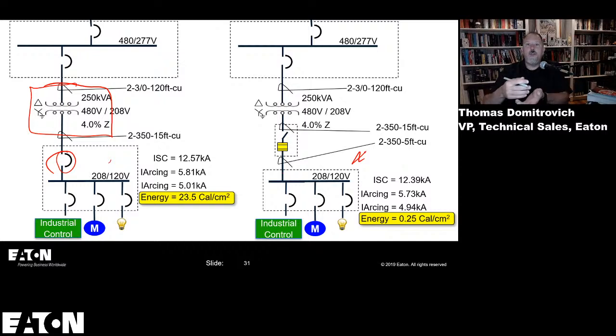I mean, even if you established an electrically safe work condition, you still have to dress and get in there and put your test probes on to make sure you turned the right breakers off, you locked and tagged the right breakers off, and all that great stuff as per NFPA 70E. By pulling this out, you have a local disconnect right next to that panel board. And it could be a panel board, it could be anything. It could be a piece of equipment that you're supplying. Pulling that disconnect switch out offers reduced incident energy, and there is more of a likelihood that you will establish an electrically safe work condition. So this is the solution.